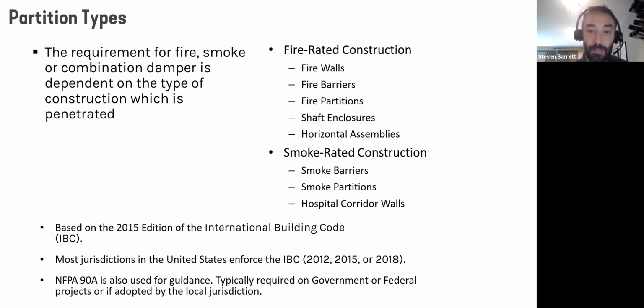So today we'll review the 5 types of fire-rated construction described in the IBC and the 3 types of smoke-rated construction. And again, we'll use the 2015 IBC, which is probably the most common in adoption right now. It might be trending towards 2018. They're on 3-year cycles, but these requirements are going to be pretty consistent throughout 2012, 2015, and 2018. And NFPA 90A we'll touch on a little bit. It's required for a lot of government and federal projects, and it's sometimes adopted by local jurisdictions. So we'll mention a couple of the key differences later on.